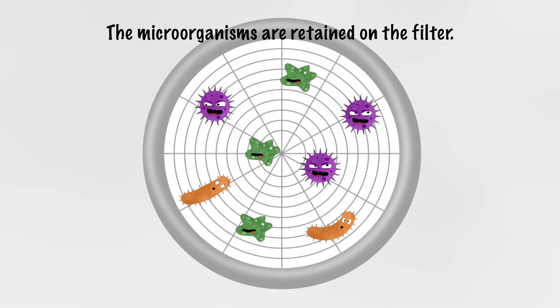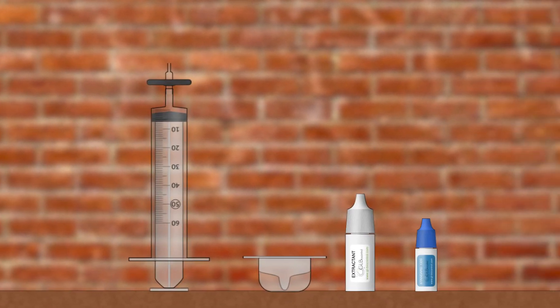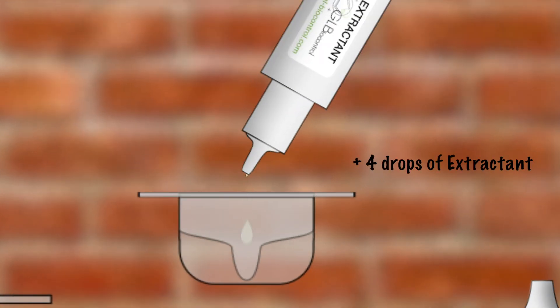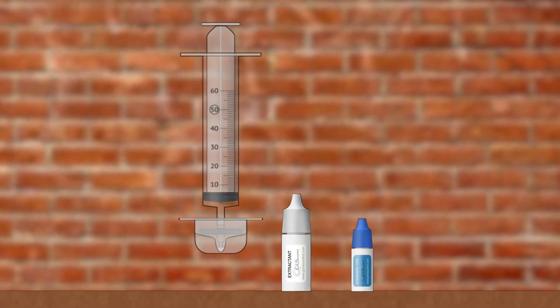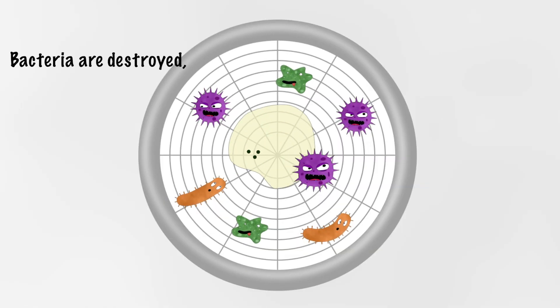The microorganisms are retained on the filter. We add 4 drops of extractant solution, then we back flush the membrane. This solution triggers cell destruction and liberates ATP.